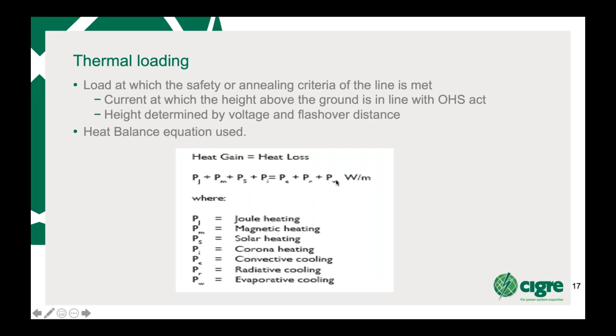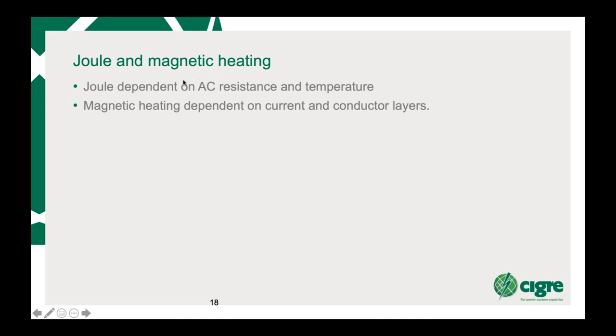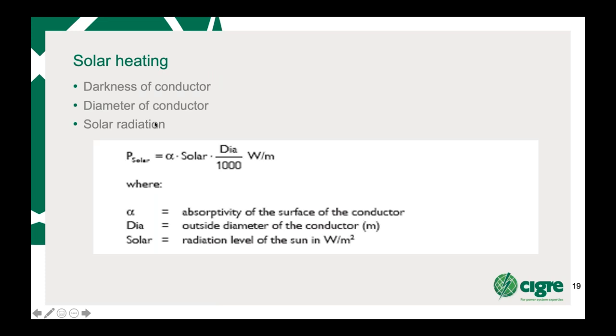So as mentioned before, Joule and magnetic heating. Joule is dependent on the AC resistance and temperature. Magnetic heating on the current and conductor layers. Solar heating depends on the darkness of the conductor, diameter, and solar radiation. So that's your P solar: your absorptivity, solar radiation in watts per meter squared, and then the diameter. The bigger the diameter, the higher the solar heating of the conductor.